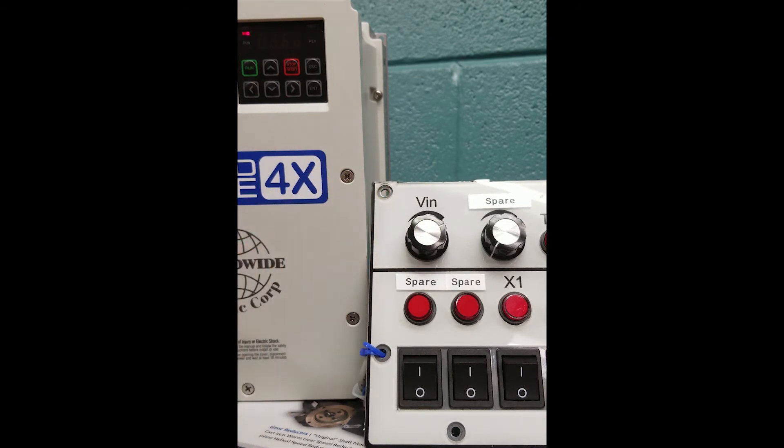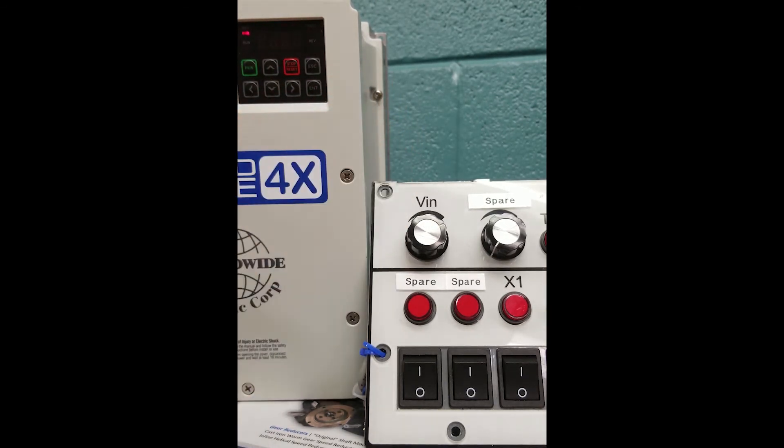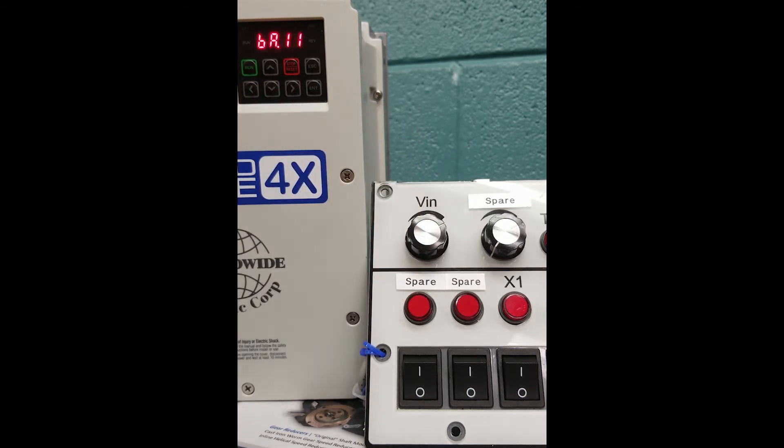We'll hit enter. Factory default is 4 pole, 1800 RPM. We could scroll down to 2 pole, 3600 RPM, or we can scroll up to 6 pole, 1200 RPM, and so on. We're going to leave it at 4 and hit enter to store that value.